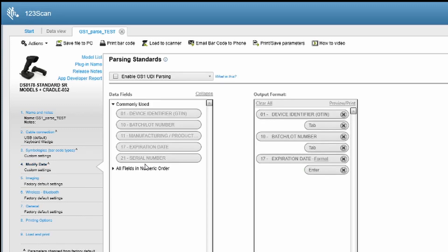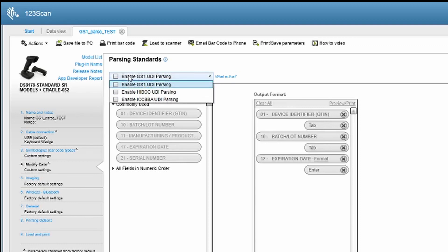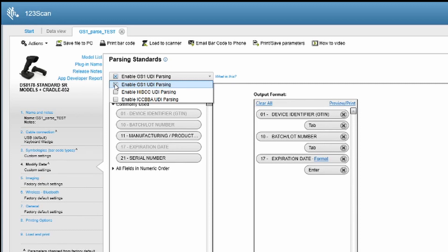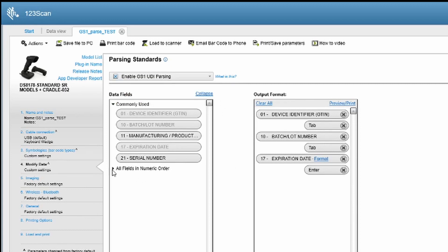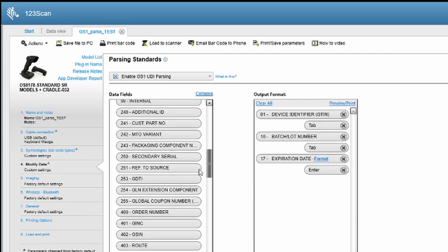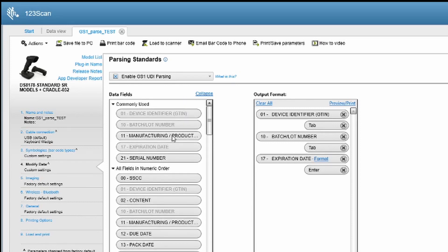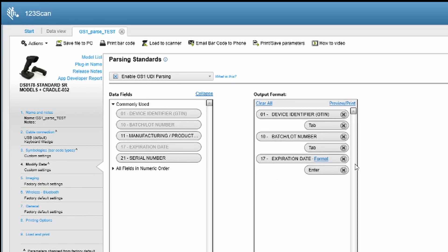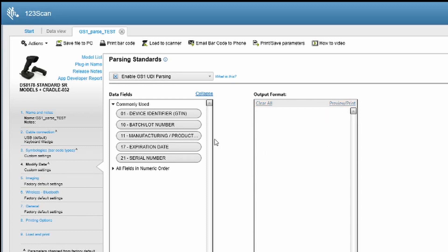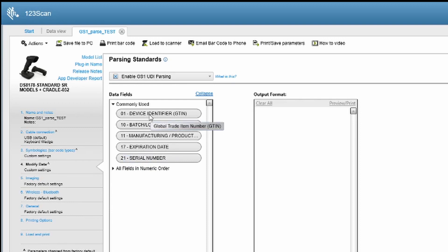Let's go in and configure. By default, there is a basic simple config already in there. If we go up to the top to initially enable the parsing rules, you'll notice there are three versions: GS1, HIBC, and ICCBBA — the three different organisations accredited to create these standards and barcodes. We're going to use GS1 UDI parsing in this case. If you tick on this fields area, you'll see there are numerous other options that can be used in these UDI codes. We're going to keep it simple and just use the ones shown here. Let's clear this to show you how simple it is. Right now we have a code that has all five of these — what we call AI codes — in it: AI codes 21, 17, 11, 10, and 01. We only want to use three of those codes.